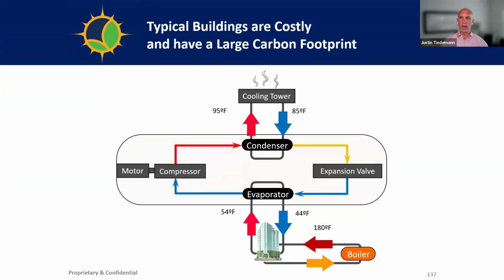A little background on commercial buildings, many of you are already familiar. Basically you have a commercial building, pumping heat in with the boiler and rejecting heat out through the cooling tower. This is the way it's done — you have open loops, and we really can't do this anymore.